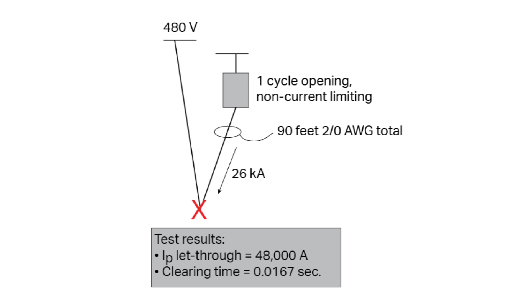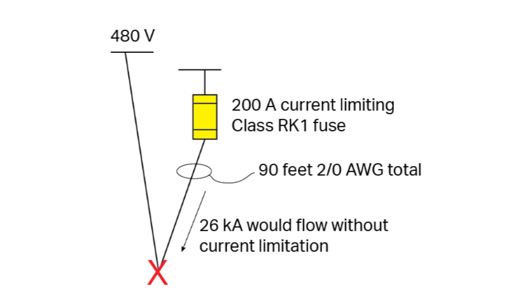In this test, the peak current let through was 48,000 amps, with a clearing time of 1 cycle or 16 milliseconds. The next test shows the same conductor but with a 200 amp class RK1 current limiting fuse upstream. You can imagine what the results would look like. Don't blink or you might miss the action.